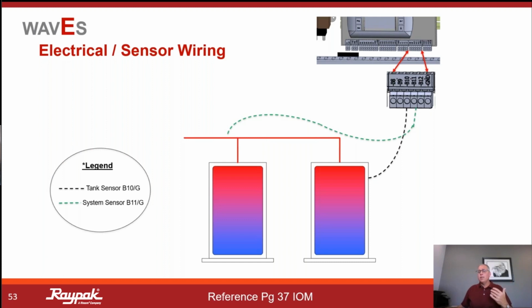So the lead unit, the leader, will have one sensor to B10 and ground. I didn't illustrate the second wire here, but these are polarity sensitive. So B10 and ground here is for my tank sensor. B11 and ground will be my system sensor. So what is my supply water as opposed to my stored water temperature? Those are the two sensors that we will be wiring from that leader.